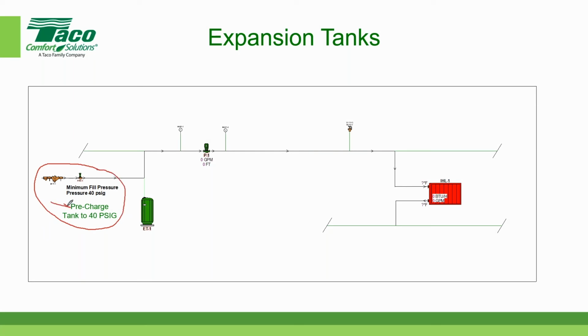It's also known as the pre-charge pressure. Now, if you remember what I said earlier, the tank comes from the factory pre-charged to 12 pounds. In this system, the tank's pre-charge pressure has to be increased from 12 pounds to 40 pounds, and we have to do that before we physically connect the tank to the piping system. It's an extremely important step.